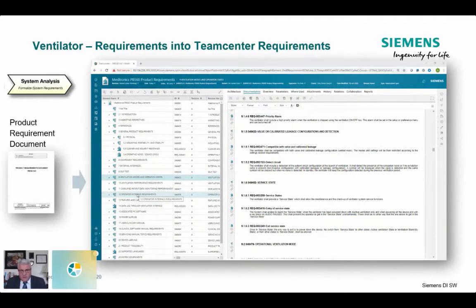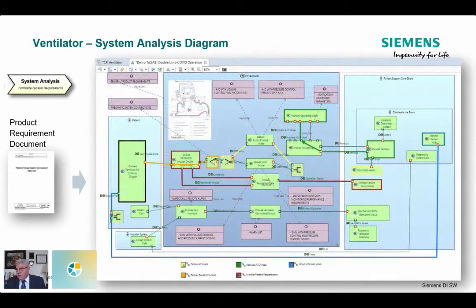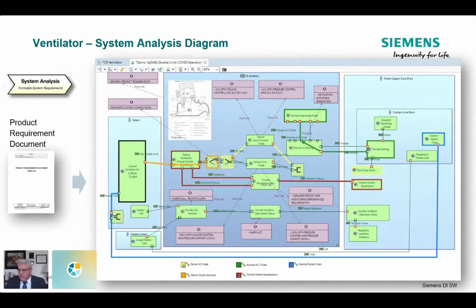There are requirements in this thing, and with our integration to Teamcenter I'm able to bring the requirements documents — the product requirements doc — into our Teamcenter product. I can then bring those requirements and integrate them with the model using drag-and-drop capability to tag things with requirements. I'm able to denote general product requirements as going to the ventilator itself, map functional requirements to functions inside the system, and also denote what's outside the system as I go through this model.